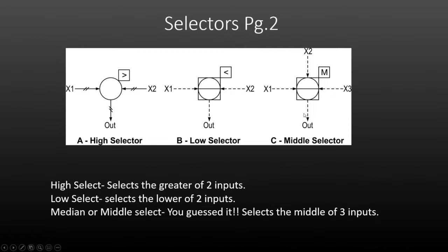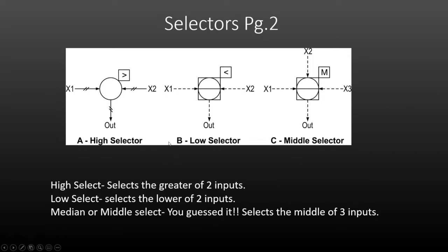The third type is called the middle or median selector, and it will pick the middle out of three measurements. So if X1 was 50, X2 was 60, and X3 was 40, it would pick the 50, which is in the middle of 40 and 60. Pretty straightforward in what they do and what their application is.